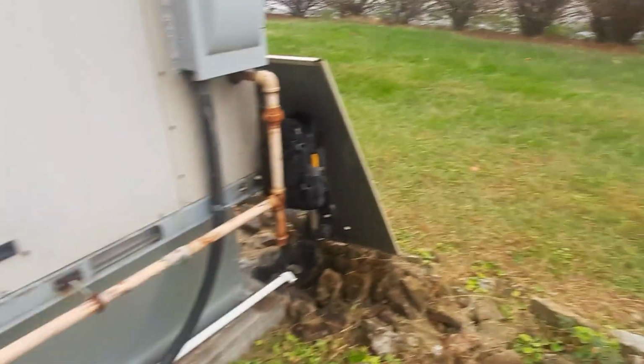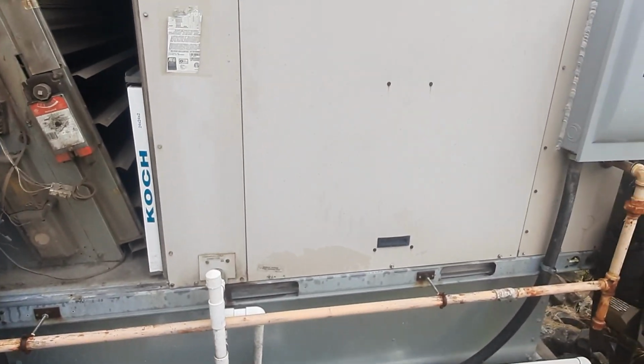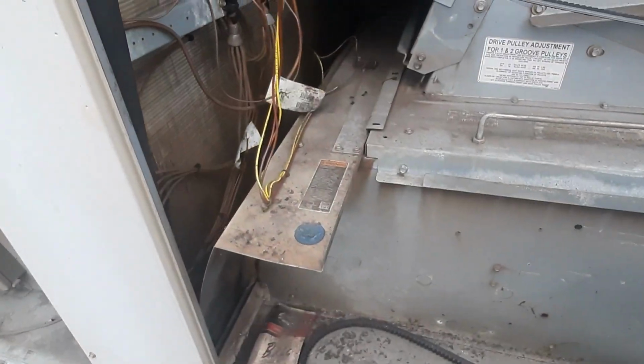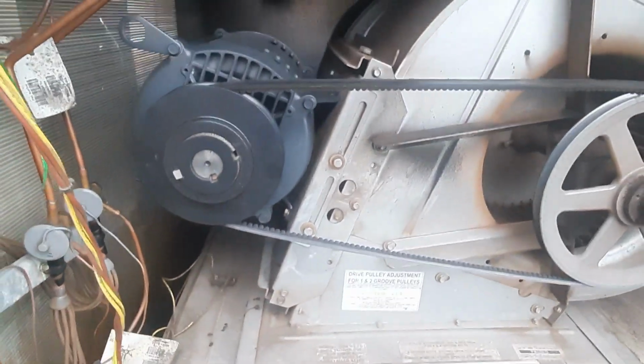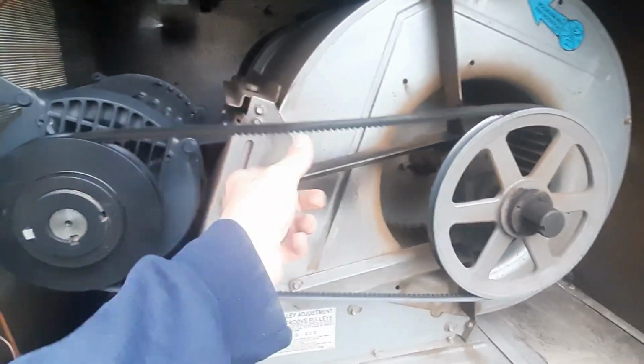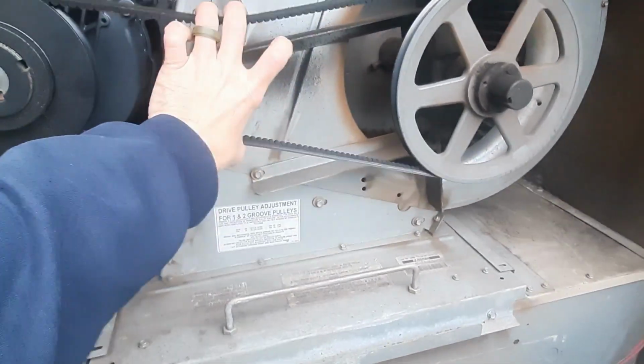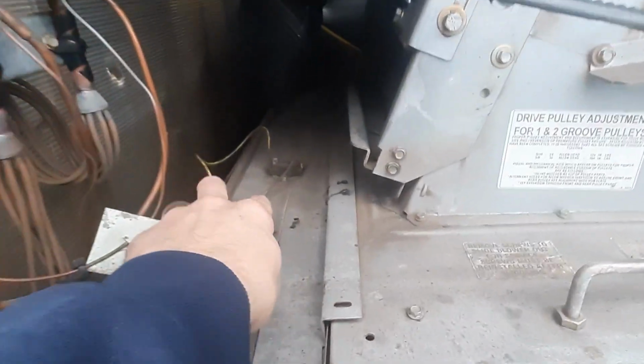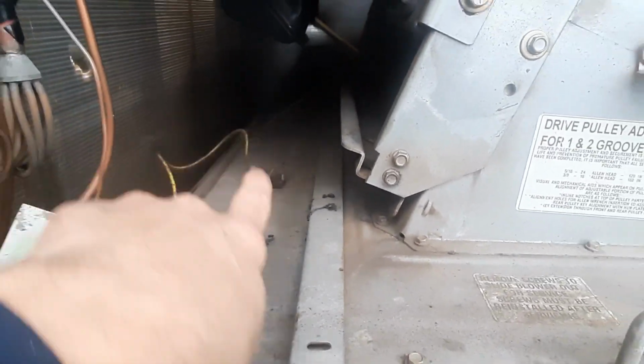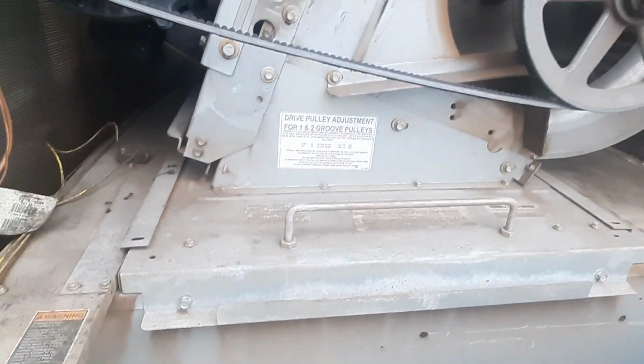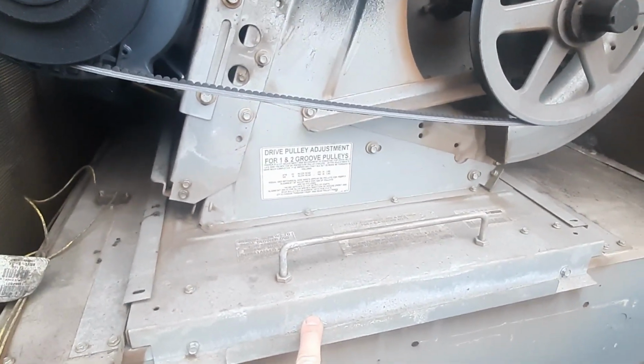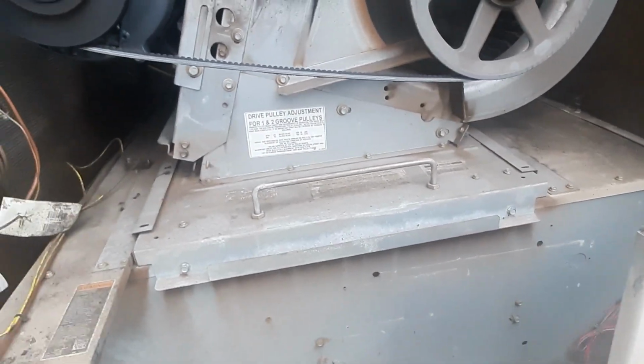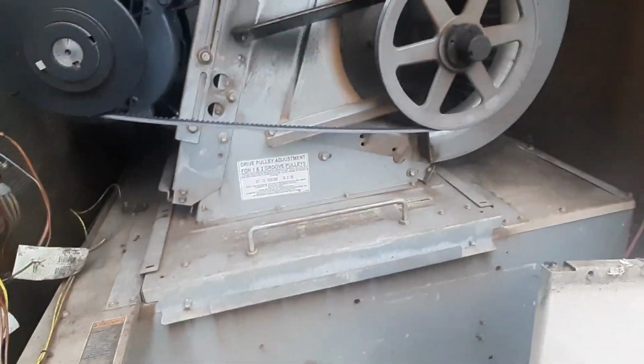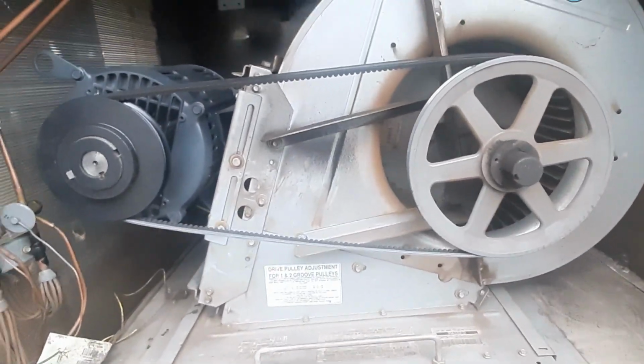So keep on moving. Let's check our blower out, see what's going on in there. I don't even know how it sounded okay or was even on. You can see it's twisted right there. And she's a bit loose. Here's our high limits in here. There's another one for the other stage back there. We might pull this out, see if I can. Actually, I'm going to hold off on that. I'm not going to try to pull that out myself. Like I said, I'm getting around pretty good, but I can't do any climbing. I've got a brace on the left leg. So this was on the ground, pretty easy for me to come out here and take a look.